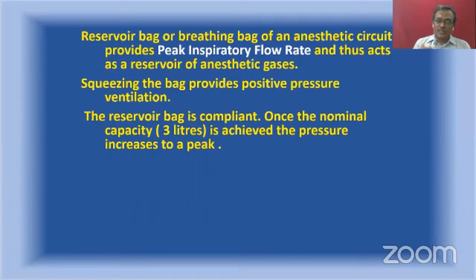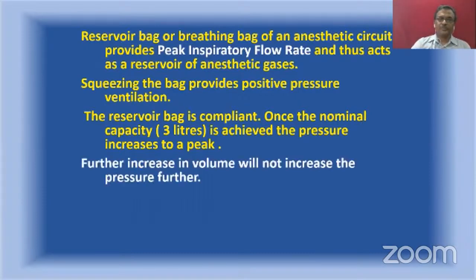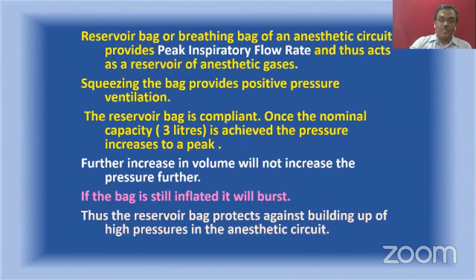It is working as a buffer in the anesthesia breathing system. How? See, once the normal capacity, let's say 3 liters, is achieved, the pressure in the system will increase to a peak. Okay? A peak pressure is achieved. And even if you increase the volume further, surprisingly, there is no increase in the pressure because the bag is compliant. Still, you are increasing the volume. What will happen? The bag will burst. So, the reservoir bag is protecting against building up of high pressures in the anesthesia circuit. So, you can call the reservoir bag a buffer in the anesthesia circuit.